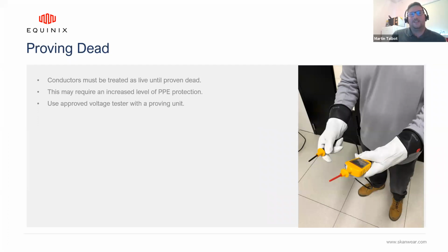On proving dead, again, we may need to increase our protection in respect to arc flash. So not just having rubber insulated gloves to protect us from electric shock, but also a leather or any other type of glove that is heat and flame resistant. The best process that I think for doing this is that when you're proving dead, the person proving dead should be the only one in the arc flash boundary. The accompanying safety person should be at a safe distance outside it, but still there to render assistance if required. He then proves dead. Once he's confidently proved dead, all arc flash restrictions can be relaxed because there are no exposed live conductors anymore. So that means that he can then escort a contractor to the point of work and then confirm dead to him without the contractor having to wear any additional PPE.